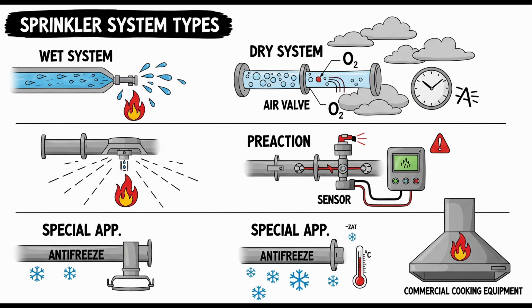Another requirement is for a low air pressure alarm, connected to signal a constantly attended location, to warn if the supervisory air pressure drops. Right. Detecting even small air leaks in the dry piping quickly is crucial before they allow significant air loss, which could potentially draw moist air into the system, or, in a pre-action system, risk a valve trip. However, this constantly attended alarm isn't necessary if the system already has local low-pressure alarms right at the valve, and it's served by an automatic air maintenance device that keeps the pressure topped up. Okay, redundancy in alarming or automatic maintenance can satisfy the need.